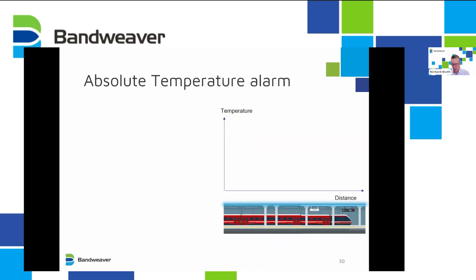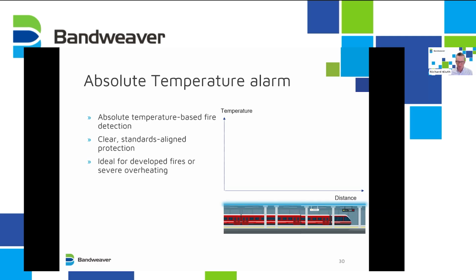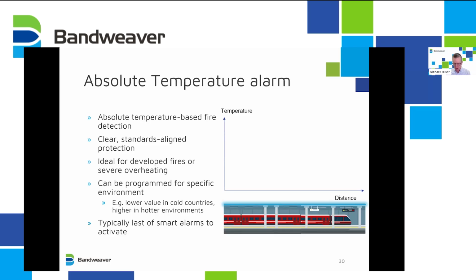So if we look at each of the alarms in a bit more detail, the absolute temperature alarm is what it says: if it goes over a temperature, it alarms. This is very much in line with a number of standards. The EN standards say this should be set 30, I think 29, degrees C above the ambient. This is good at developed fires, or where we have very severe overheating. You can program it in our case for specific environments. So as I said, you might set it lower in cold countries, higher in hotter environments, or different zones within the installation where they may be different. And it's typically the last of the smart alarms to activate, so the least responsive, but your safety net, so to speak.